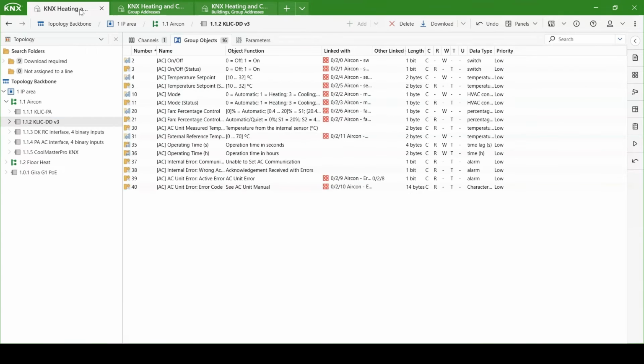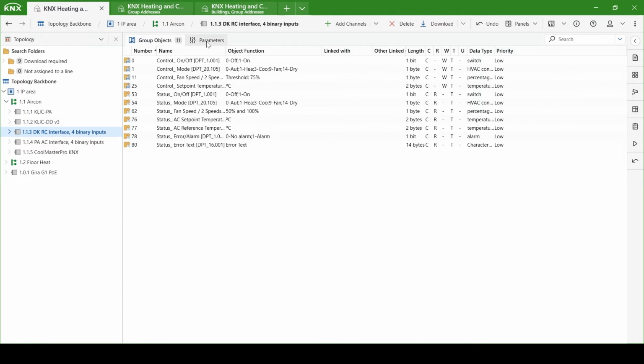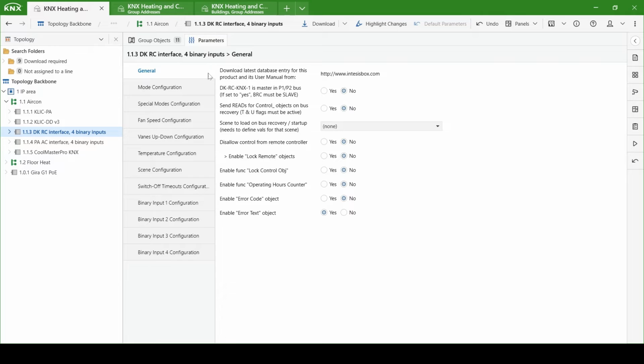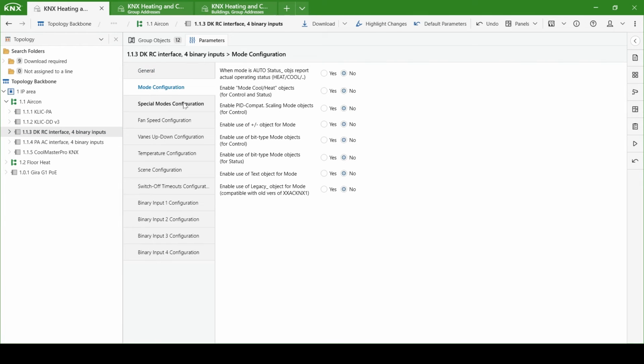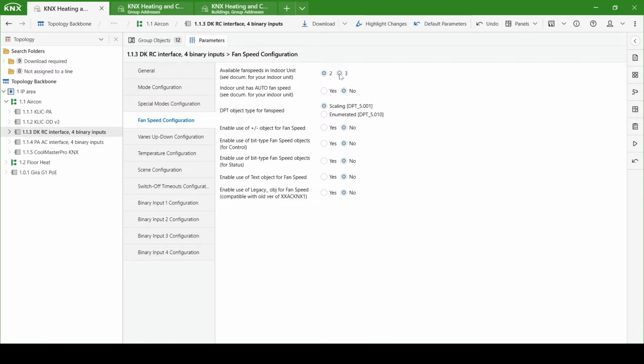Going back, I wanted to show you the similarity and convention that's the same with Intesis, for example. If you look at Intesis, it's pretty much the same thing, just asked a different way, but very similar, so you don't get lost from brand to brand. It asks whether it's P1 or P2, whether it's a slave or a master, and you can enable different parts of the gateway for different functions. One important thing to point out is you always have to enable what type of fan speed it is depending on the aircon.